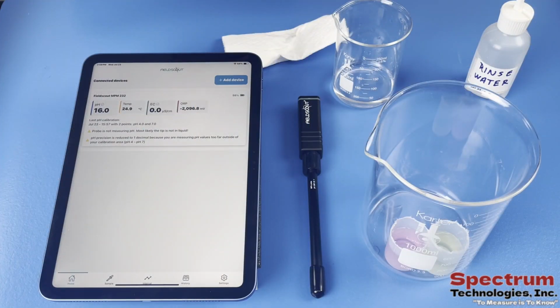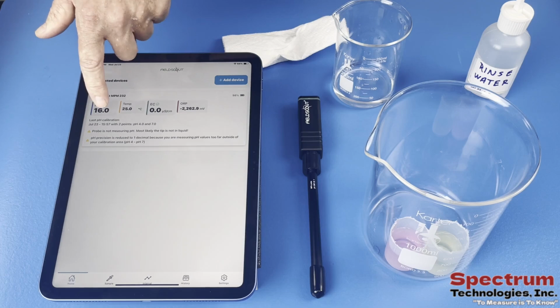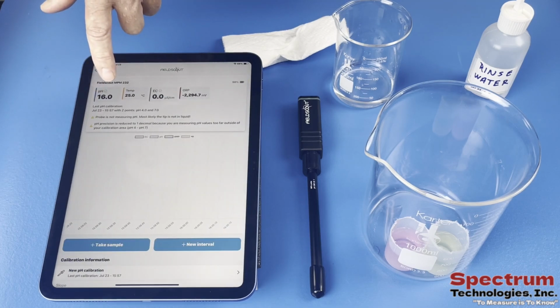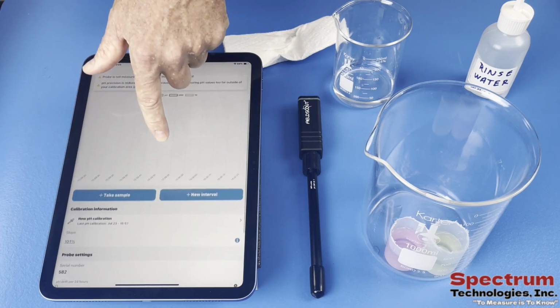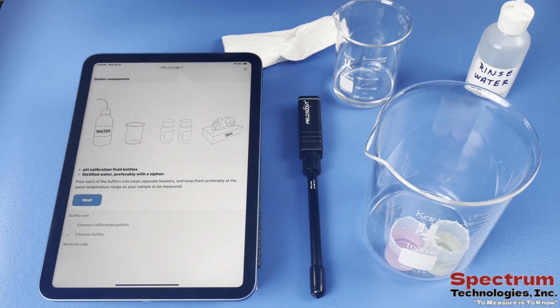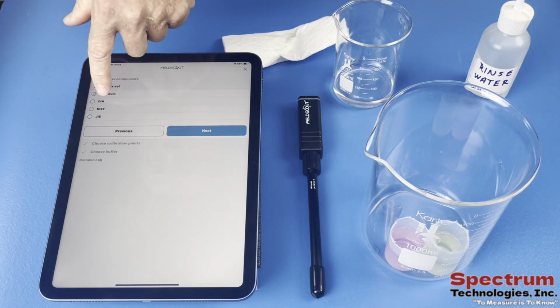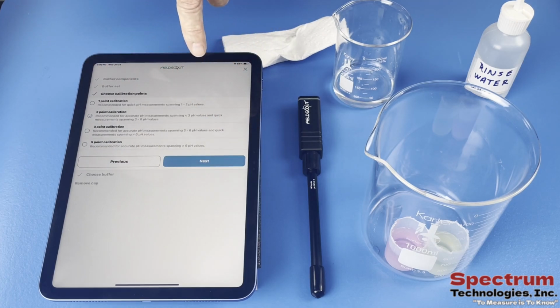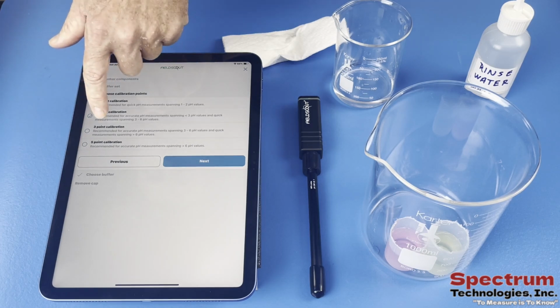With the app open and your probe connected via Bluetooth, follow these steps to calibrate the probe. You can perform a 1-point or 2-point calibration. In this video, for greater accuracy, we'll be doing a 2-point calibration using pH 4 and pH 7 buffer solutions. In the app, tap on any of the data fields. Scroll down and select New pH Calibration. Follow the on-screen prompts. Tap Next, then select the Spectrum buffer set. Choose the 2-point calibration and select pH 4 and pH 7 as your reference values.